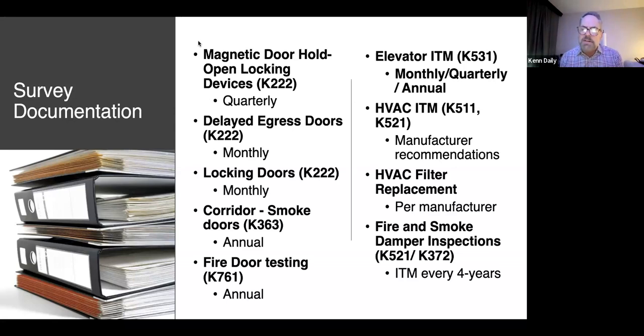And then you have your elevator. Now, most of your quarterly and annual inspection by elevator are done by a contractor, but you have the monthly fireman recall testing. This has come up now. I mean, most states are enforcing this now, that you have to go in with the key, turn that key, and you have to make sure that elevator recalls back to the floor of egress each month. So you have to have documentation of that elevator recall.